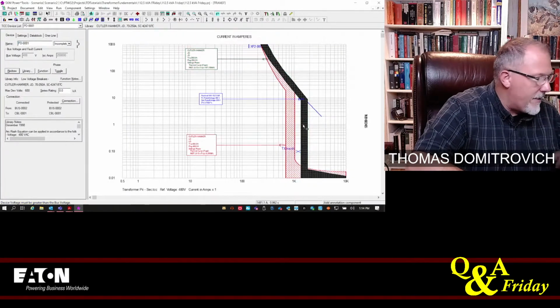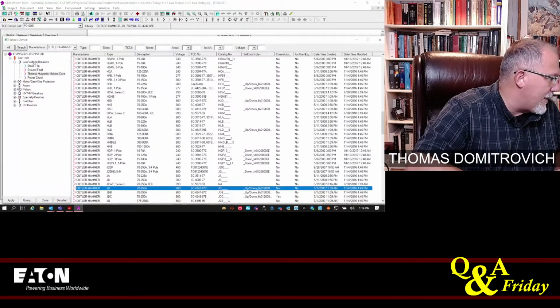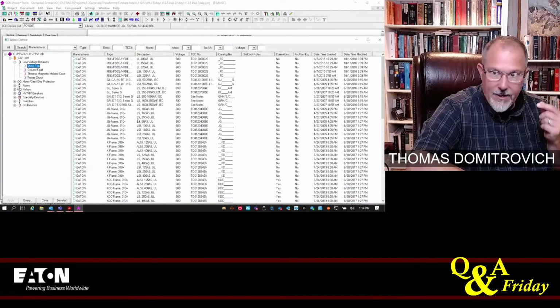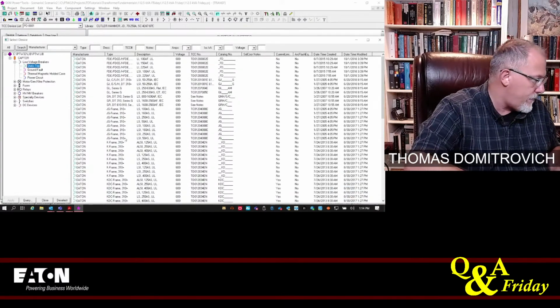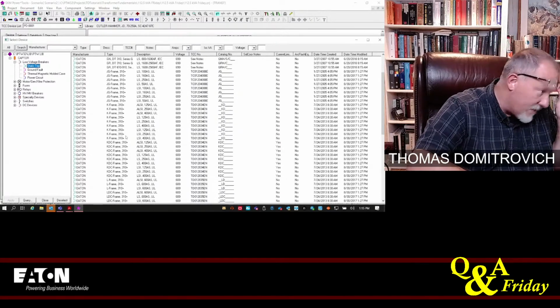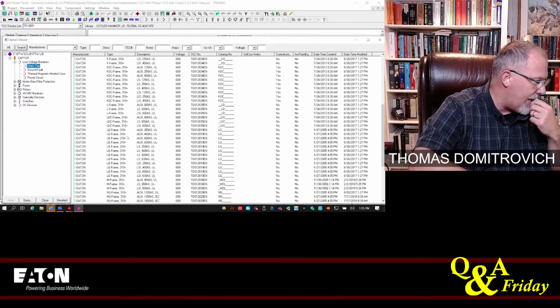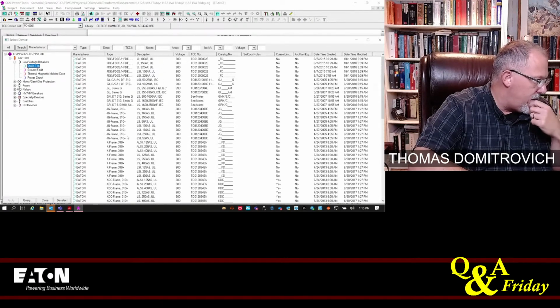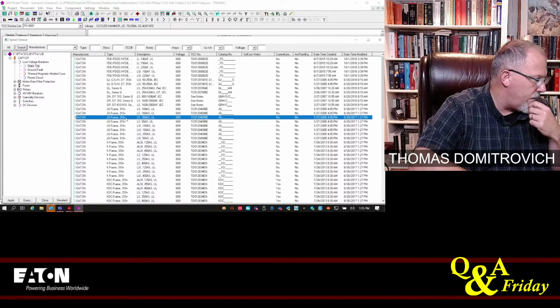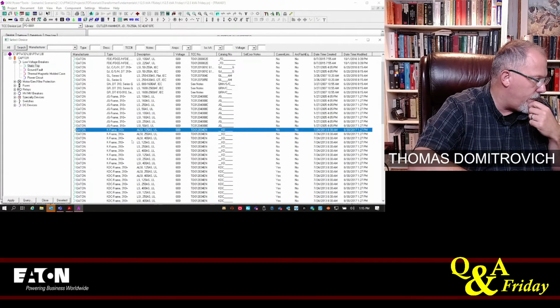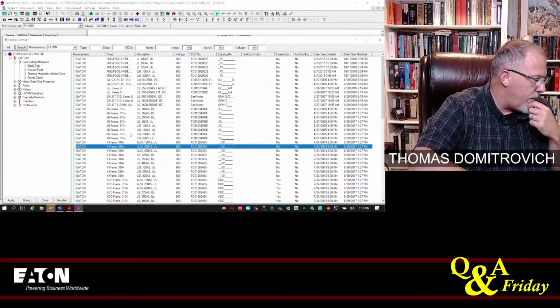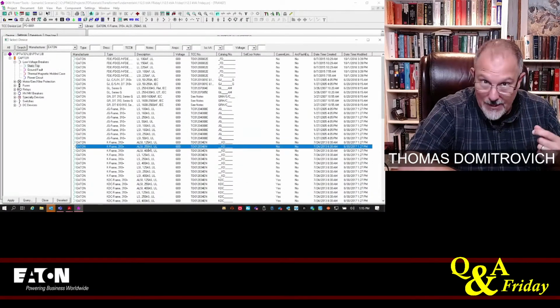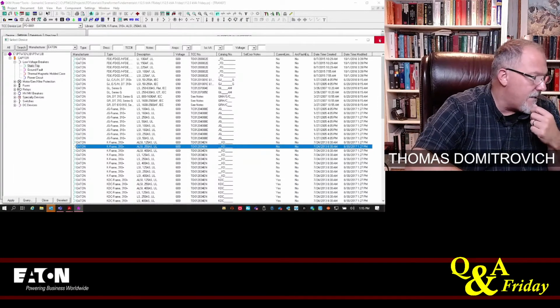Now we're going to take this primary device and go back to the library, and we're going to put an electronic trip unit in it. What is that primary? We said it was 200 amps, right? So let's try a... Here we go. See that ALSI? A is for arc reduction. And I'm going to see if we can model that.